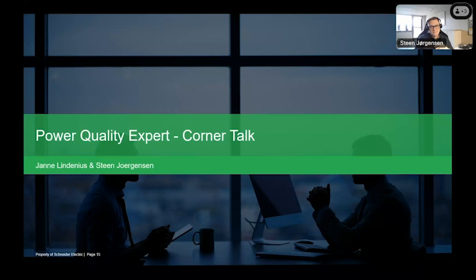Fantastic, good to hear. So what kind of effects are there from imperfect power conditions for the customer? Yeah, imperfect power can do a lot of damage for sure, because we can actually overheat our transformer or our UPS system or generators, and we can get the control system to do something wrong in the facility, or we can have motor failure, and have a lot of nuisance in the factory. And for sure, one of the biggest nuisances is if we have some shutdowns, if we have a blackout.